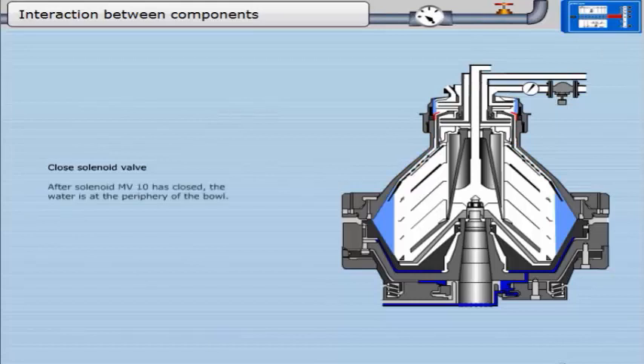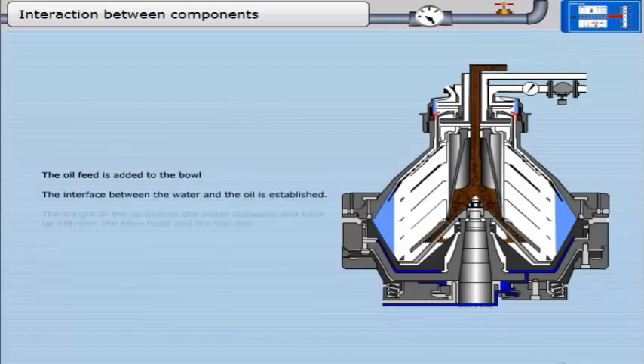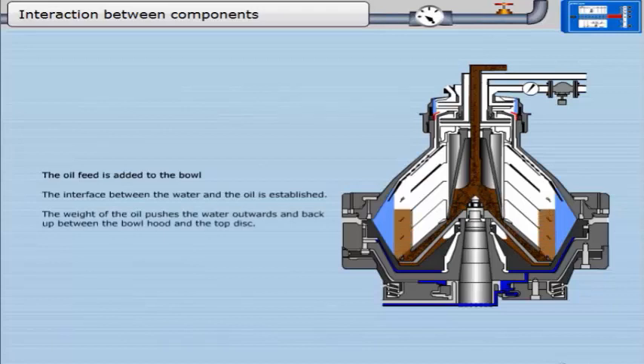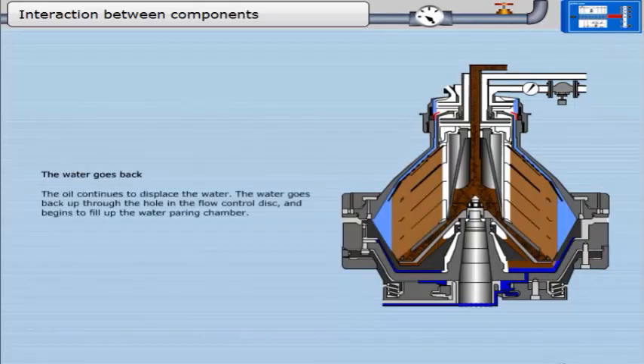After solenoid MV10 has closed, the water is at the periphery of the bowl, with a small amount also in the water paring chamber. The interface between the water and the oil is established. The weight of the oil pushes the water outwards and back up between the bowl hood and the top disc. The oil continues to displace the water, which goes back up through the hole in the flow control disc and begins to fill the water paring chamber.